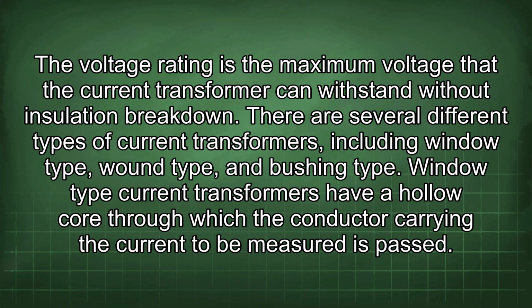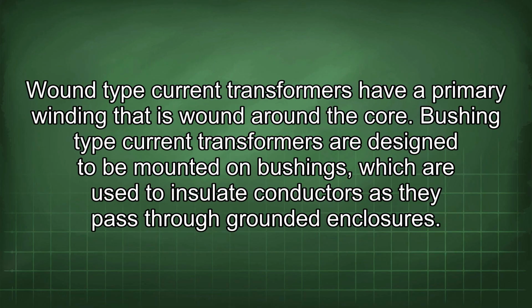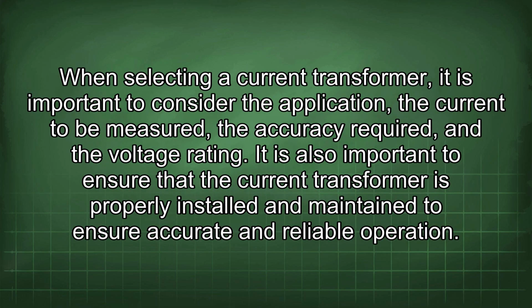There are several different types of current transformers, including window type, wound type, and bushing type. Window-type current transformers have a hollow core through which the conductor carrying the current to be measured is passed. Wound-type current transformers have a primary winding that is wound around the core. Bushing-type current transformers are designed to be mounted on bushings, which are used to insulate conductors as they pass through grounded enclosures. When selecting a current transformer, it is important to consider the application, the current to be measured, the accuracy required, and the voltage rating. It is also important to ensure that the current transformer is properly installed and maintained to ensure accurate and reliable operation.